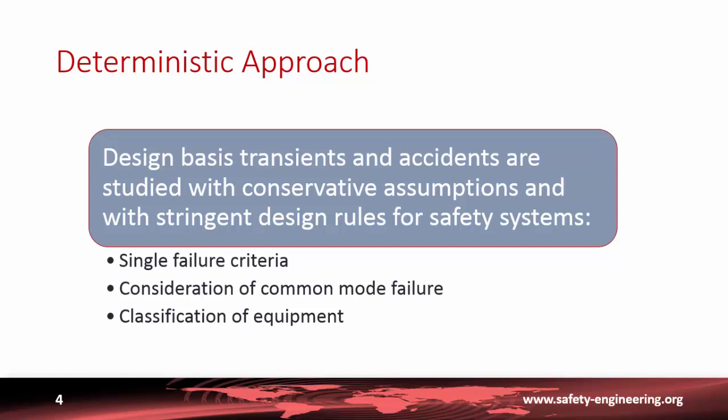An important design rule is the quality of the equipment of the safety system. Equipment needs to be classified in terms of quality design and procurement, but also in terms of qualification, because if the system has to operate in an accident environment, it should be qualified to sustain that environment, for instance in terms of temperature or pressure.